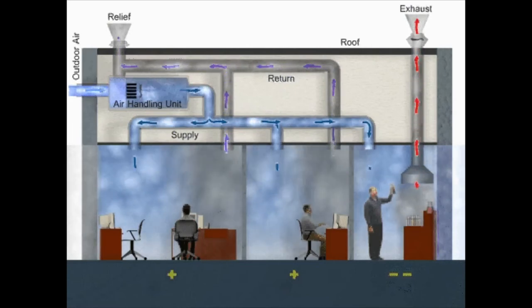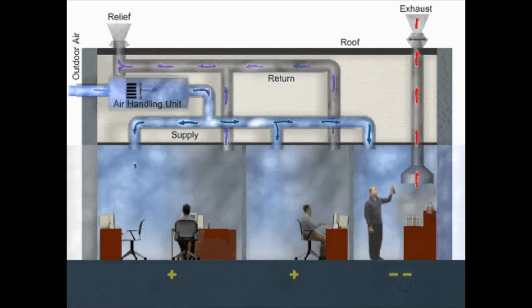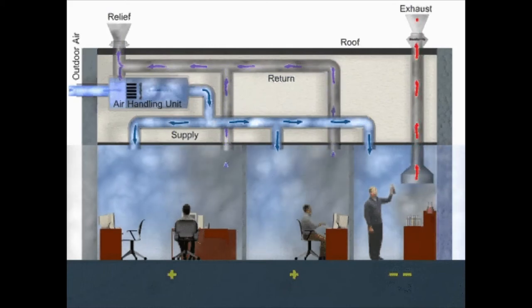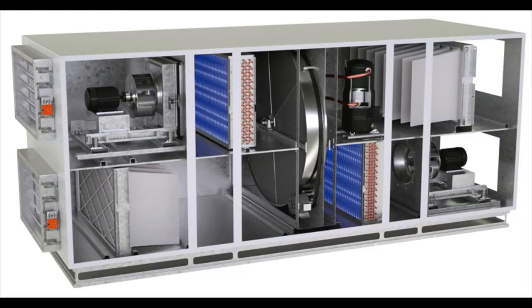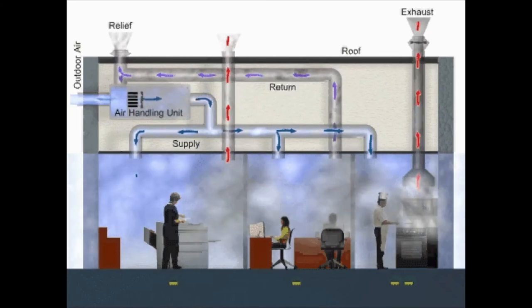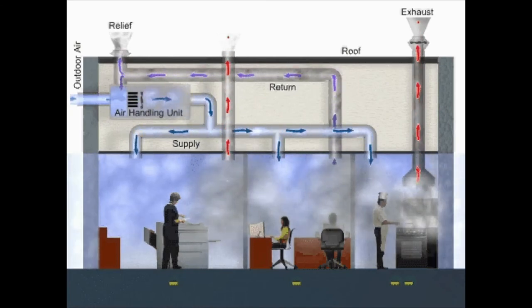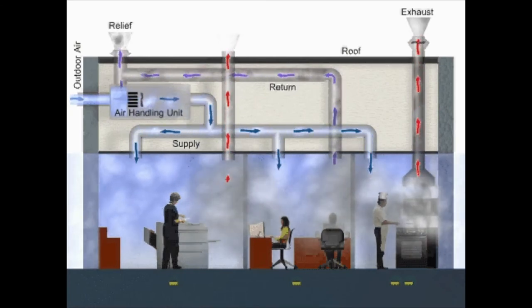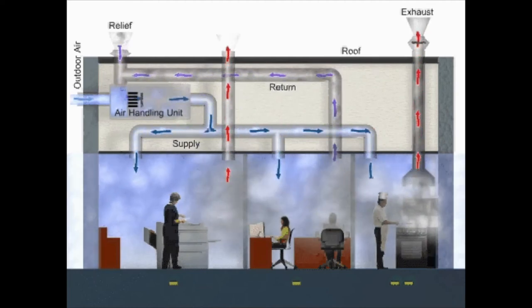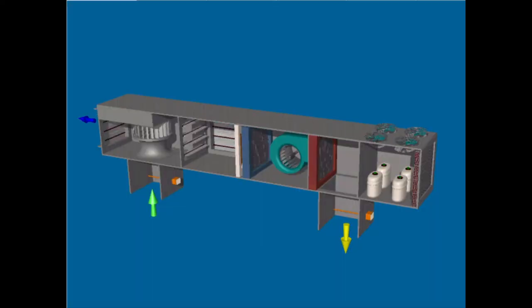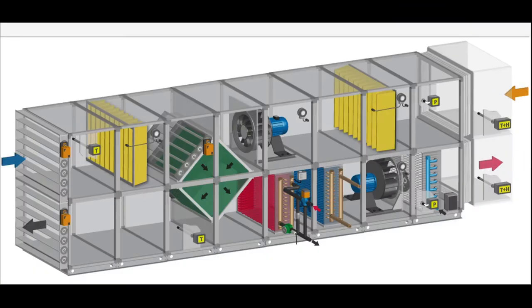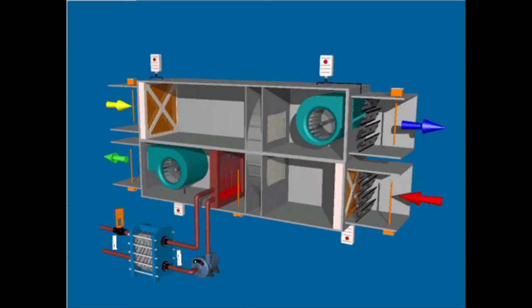That brings up another important thing that I almost forgot, actually. So dedicated outside air systems, or even a system that was not designed for dedicated outside air but is capable of it, especially in conditions like today where the temperatures are dropping and they're not too hot, you can turn them into economizer mode. And by the way, economizer mode is when your system is just going to bring in 100% outside air into the building, and it's going to exhaust all that air back out.